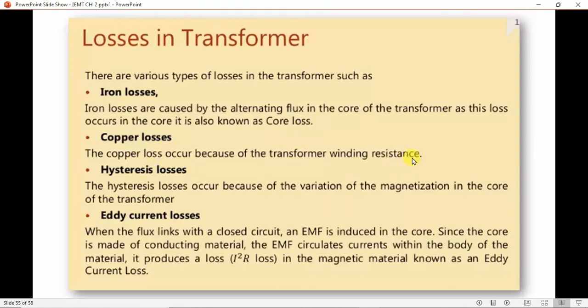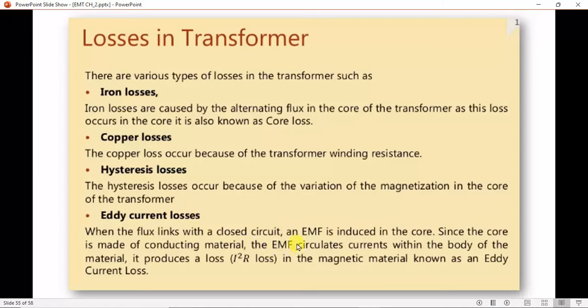Copper loss is due to the transformer winding resistance — the I²R loss. Hysteresis loss is caused by variation in magnetization in the core due to the repeated process of magnetizing and demagnetizing. Eddy current loss occurs when flux links with the closed circuit of the iron core — since iron is a conducting material, the induced EMF circulates currents within the core body, producing eddy current loss.